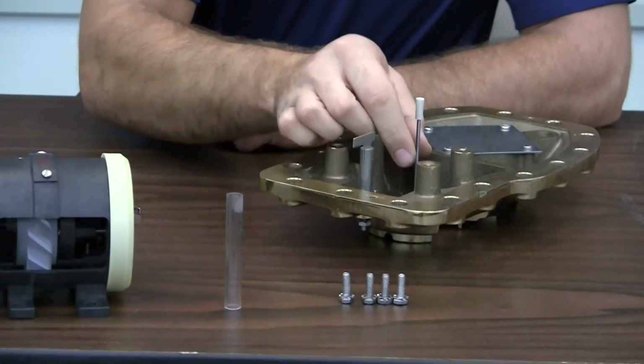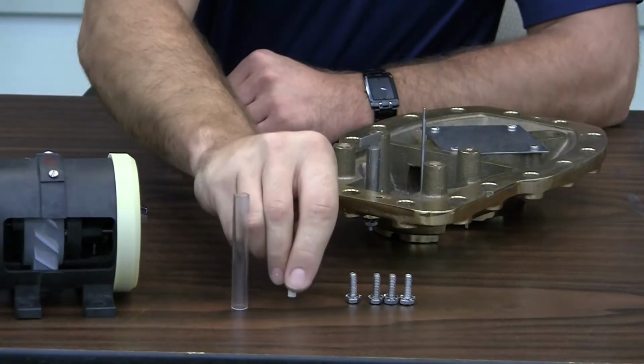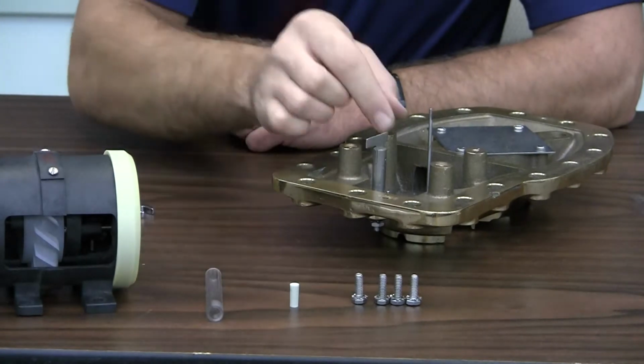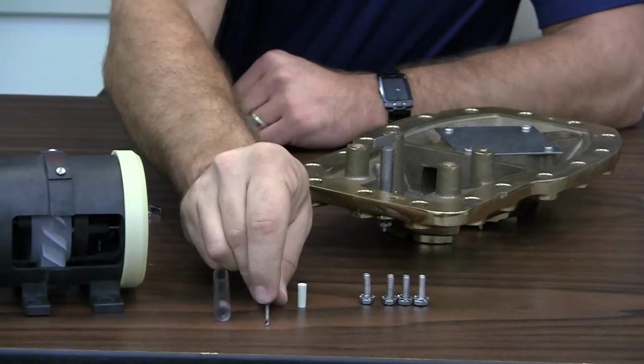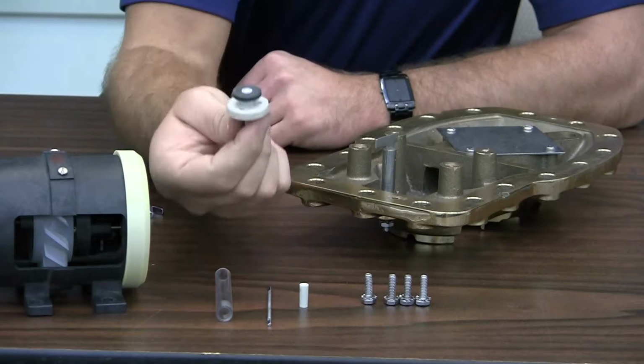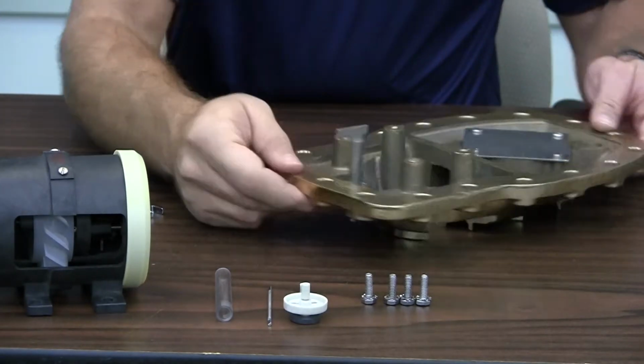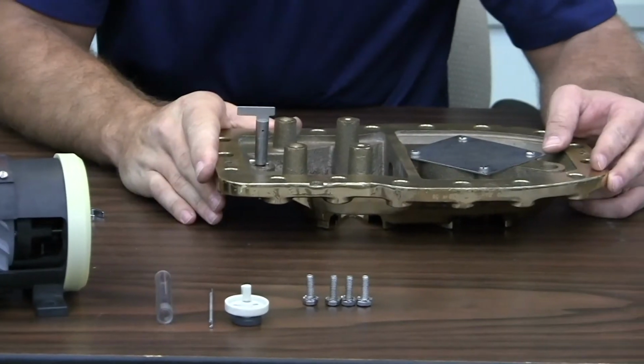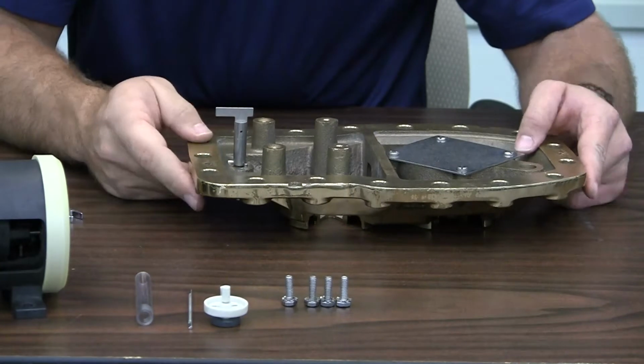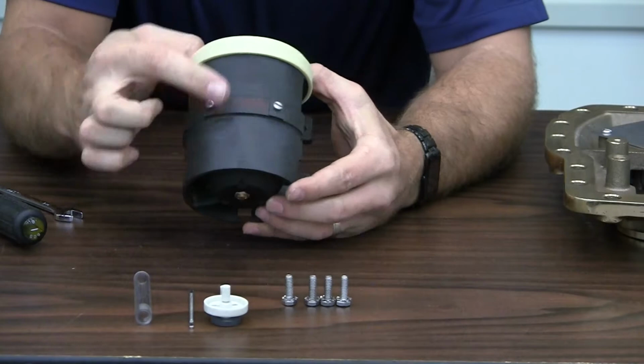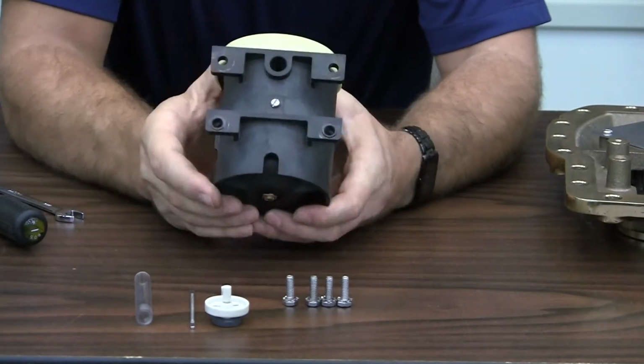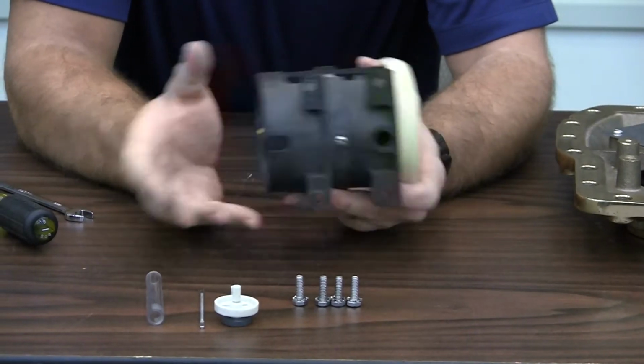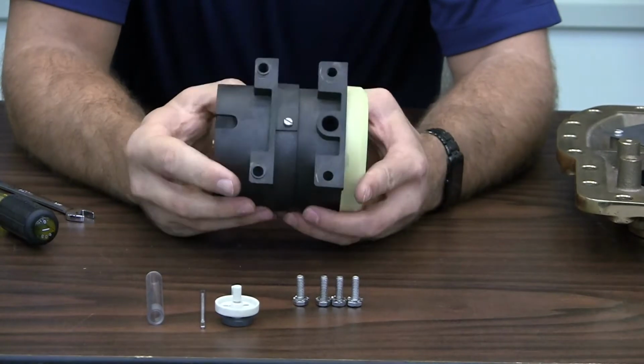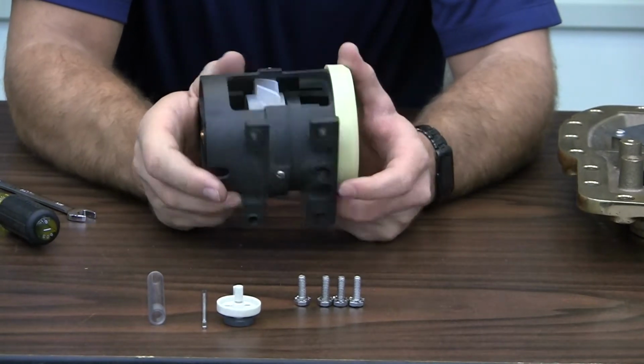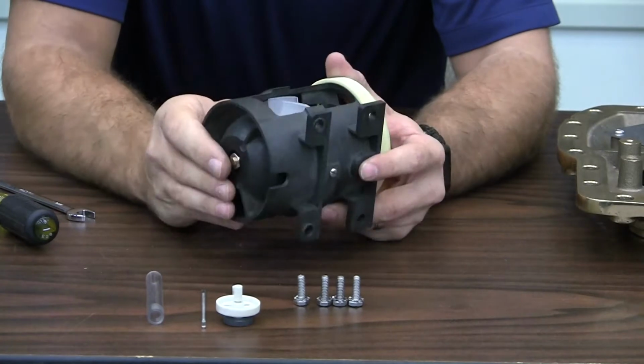protective sheath that goes over the magnet drive, magnet gear coupling, stainless steel drive, and of course the magnet assembly. That completely breaks down everything from the main case, but we'll go a step further and we're going to break down the turbine assembly. There's 3 screws that hold the turbine assembly together. To take this apart, you don't have to take the screws all the way out. You can just loosen them so the 2 chambers can come apart, or the 2 halves can come apart.